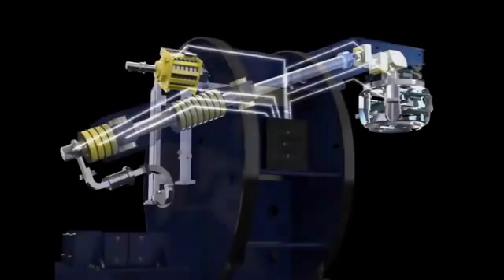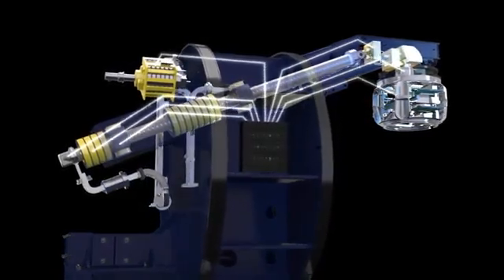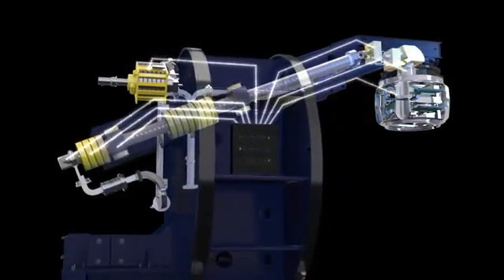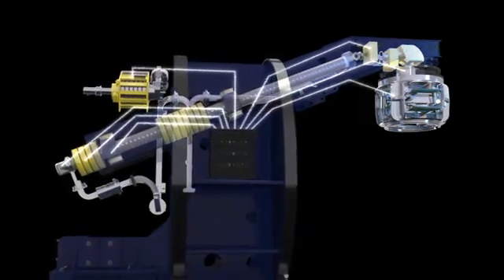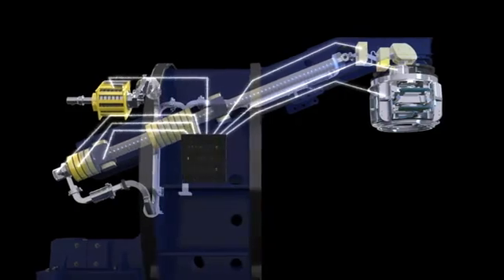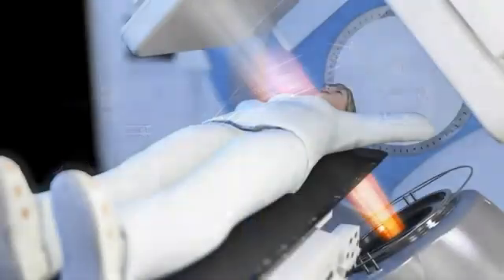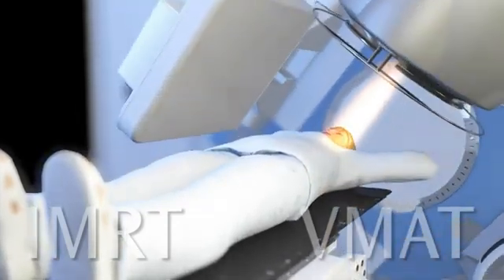LINAC control. One computer system controls both the LINAC and the multi-leaf collimator. This eliminates dosimetric errors due to communication delays. It also ensures synchronization between the delivered dose and the multi-leaf collimator position, allowing complex deliveries such as intensity modulated radiation therapy and volumetric modulated arc therapy.